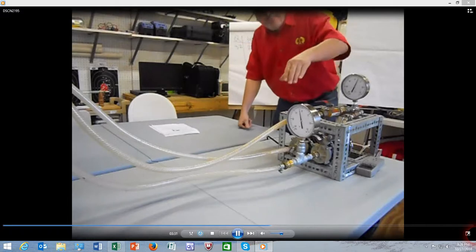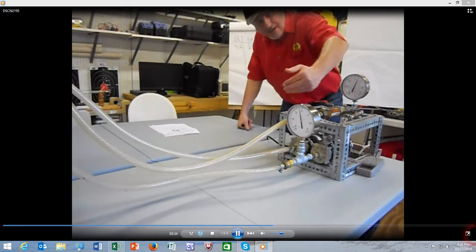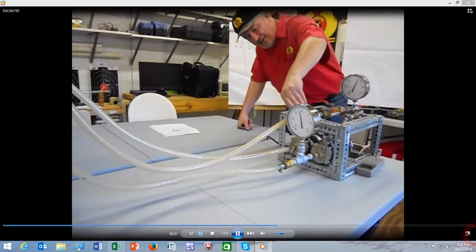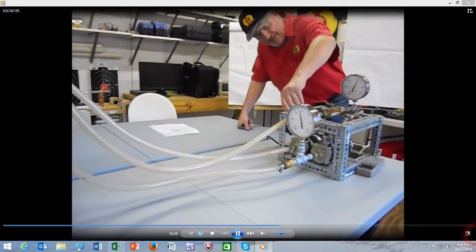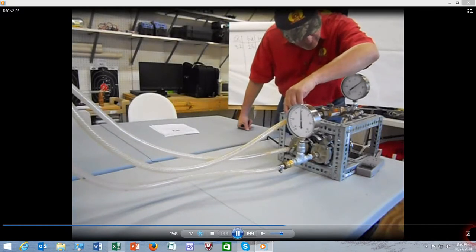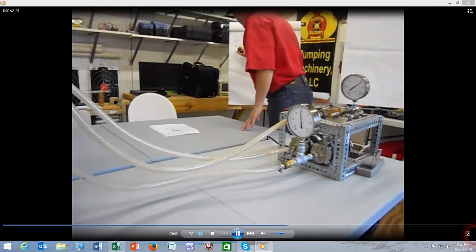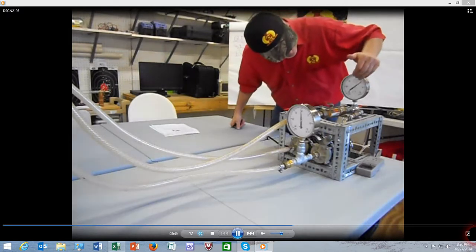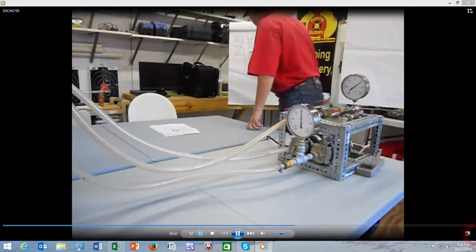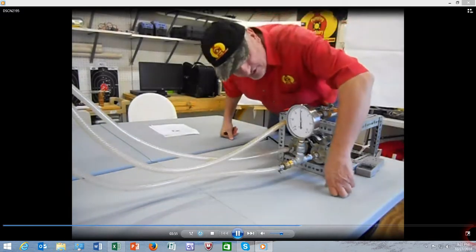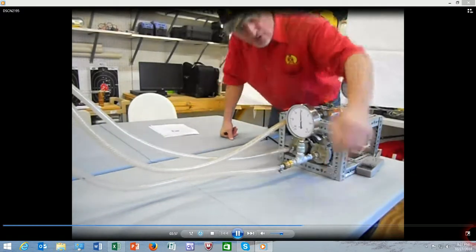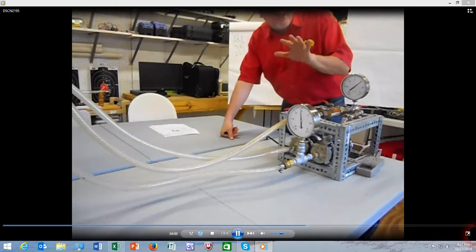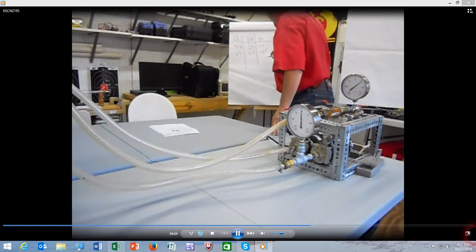We're going to pinch the valve on the discharge side a little bit. The valve is behind the gauge. I'm going to pinch it slightly. And the flow went to about 2.5 gallons per minute. You can see the discharge pressure went to, let's call it, 5.5 psi. The suction pressure is approaching zero, maybe minus 1 inch of mercury, which is roughly half a psi, minus 0.5 psi.